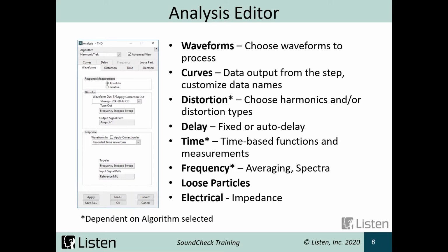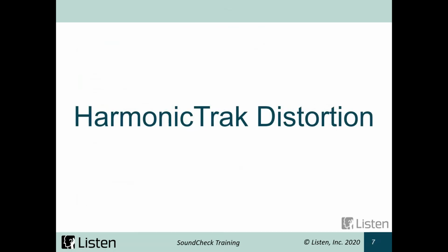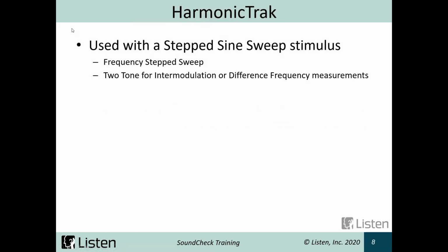What we're going to concentrate on today a little bit more in depth is first looking at the Harmonictrak algorithm and the Distortion tab. So with Harmonictrak, we need to use a stepped sine sweep stimulus. There's a couple different options here.